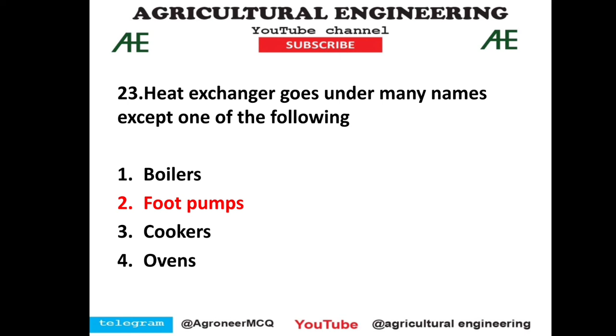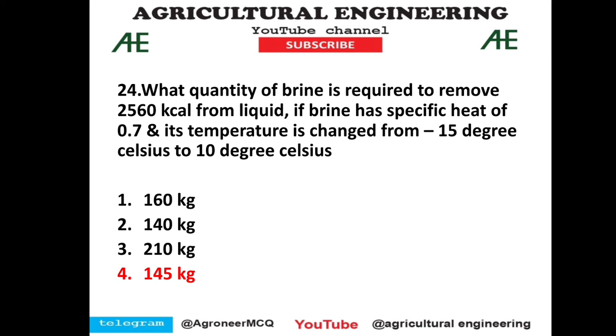What quantity of brine is required to remove 2560 kilocalories from liquid if brine has a specific heat of 0.7 and its temperature is changed from -15 degrees Celsius to 10 degrees Celsius? Here we can find this quantity by using m Cp delta T. We want to find m. Cp is given, specific heat is 0.7, and delta T we can find by 10 minus -15. So you will get the answer.